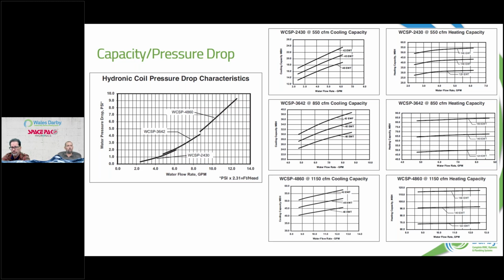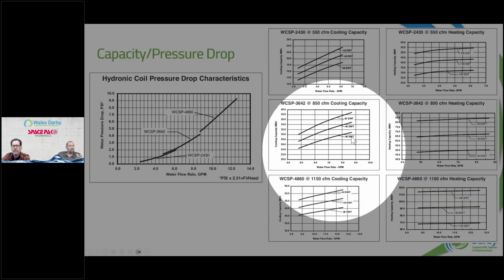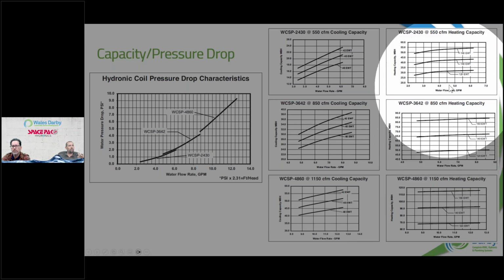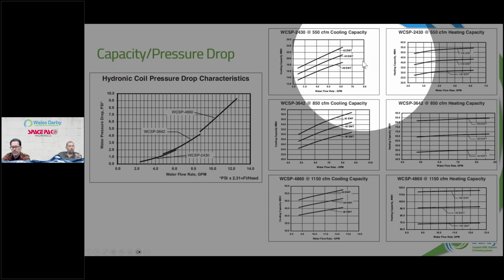If you look at the charts on the left and the right, we'll do the pressure drop after this, we'll do the capacities. You can see our cooling capacities here and our heating here. Based on the GPM we're flowing to these air handlers, you can see we give you an entering water temp, so this is entering the actual air handler at 120 degrees, 140 degrees, or a bit higher. Based on whatever you were putting into it, those are your BTU values. You can see cooling here, so that's chilled water. So a couple different charts here.